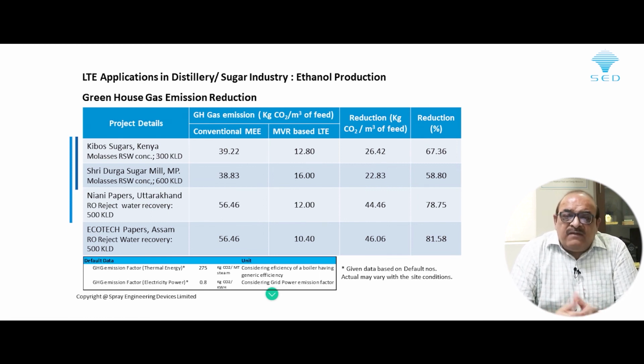For the conventional multiple effect evaporator, the load comes to 39.22 kg CO2 per cubic meter of feed in case of Kibos, whereas for the MVR LTE application, it is only 12.8. Similarly, for Shri Durga Sugar Mills, both being spent wash concentration applications, you find 38.83 kg CO2 per cubic meter for the conventional system against 16 kg CO2 per cubic meter for the LTE based system.